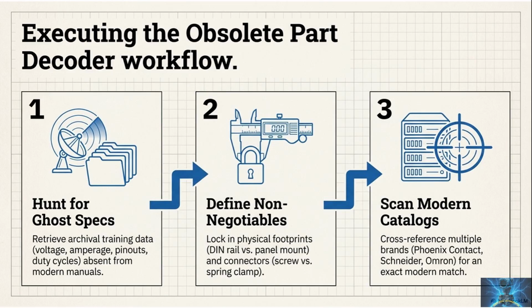Executing the obsolete part decoder workflow. This is a simple 3-step workflow for obsolete parts. Step 1. Hunt for ghost specs. Find the missing details that modern manuals don't include. This includes voltage, amperage, pinouts, duty cycles, and any hidden constraints. Step 2. Define non-negotiables. Physical footprint and connection style. This means DIN rail versus panel mount and screw terminals versus spring clamp. Step 3. Scan modern catalogs. Cross-reference across brands for a true match. This prevents it-fits replacements that fail on ratings, wiring, or environment.